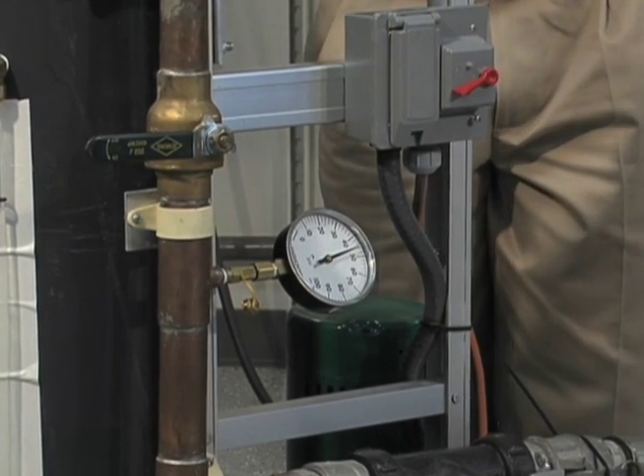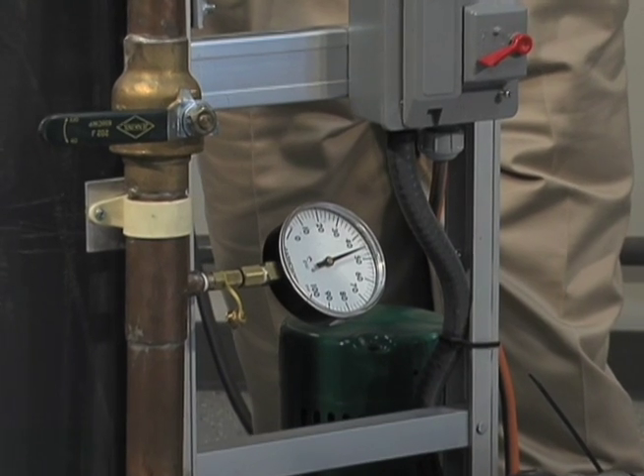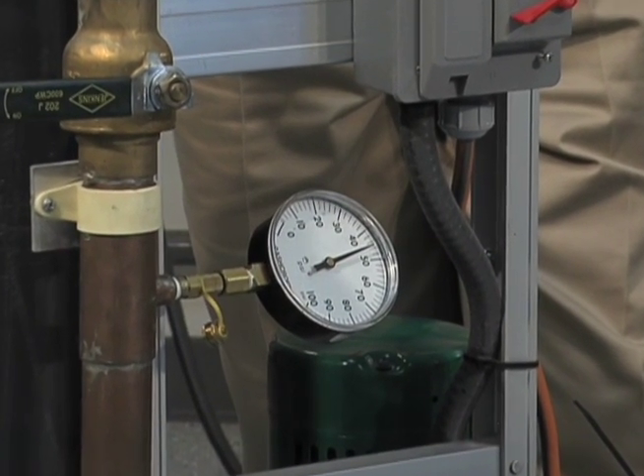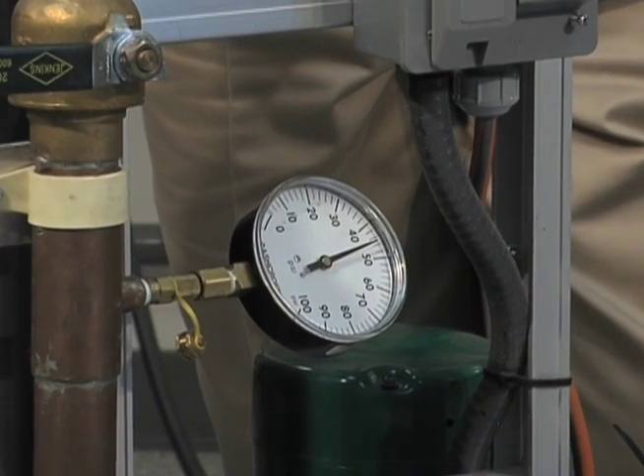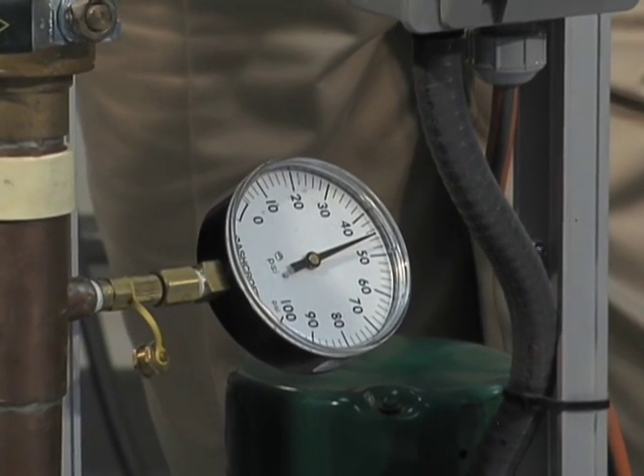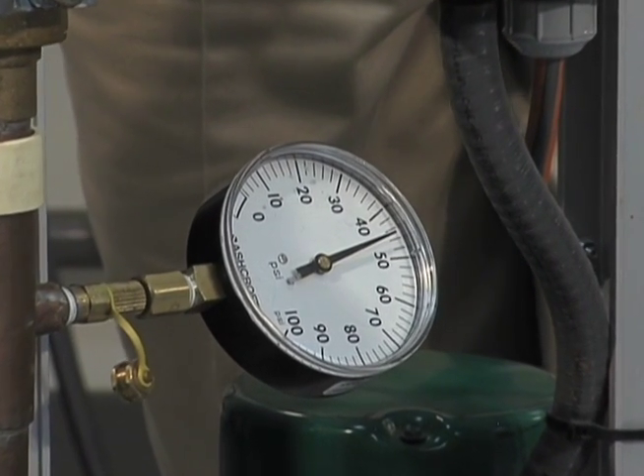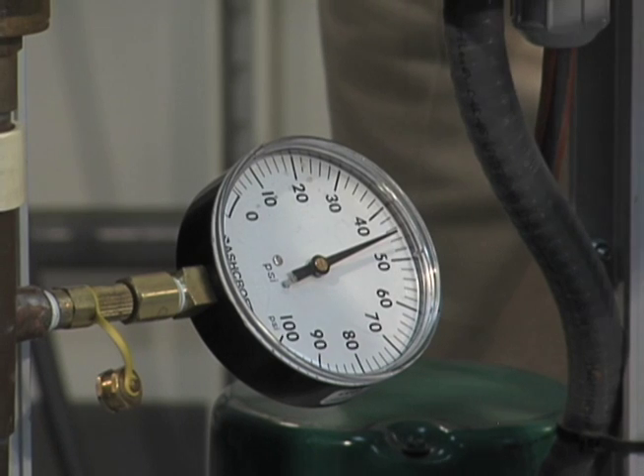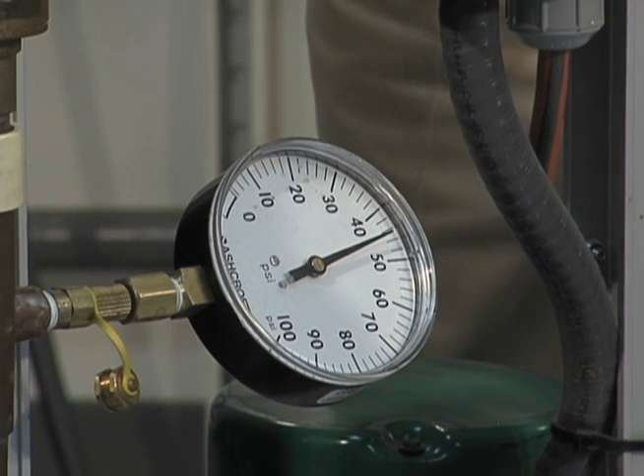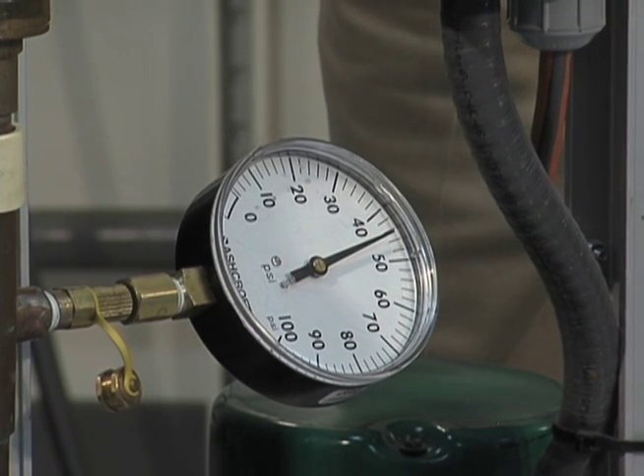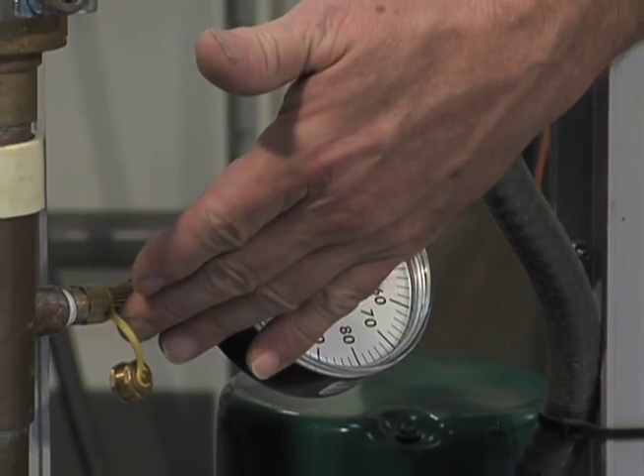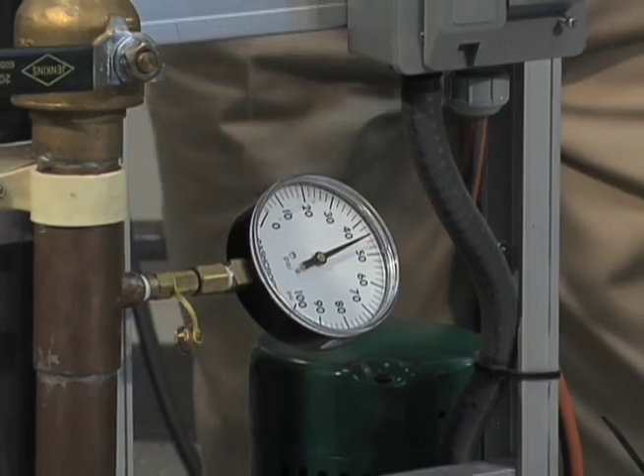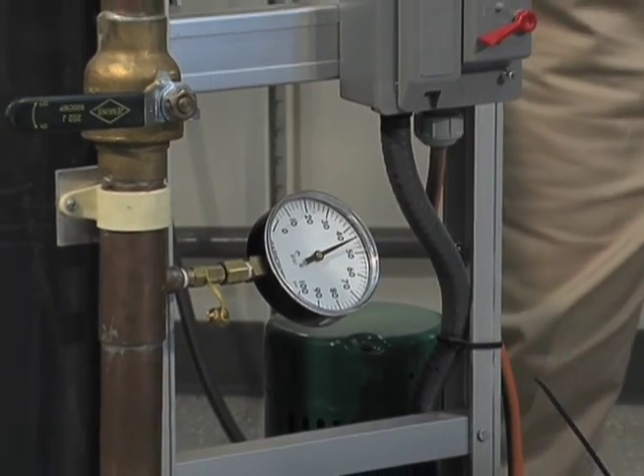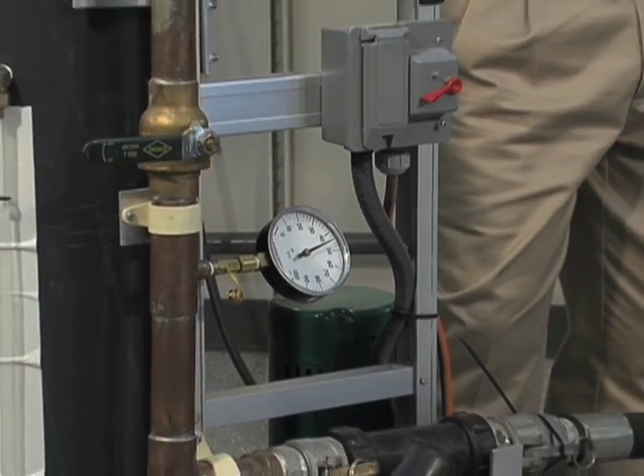If we have an excessive amount of air in there, we're going to see some movement on that needle. It's not unusual to see a little bit of creep on that needle over a few minutes just as things start to settle down. If you have any components on your flush cart that may leak, you may want to reconsider and take this pressure gauge out. Again, it slides through that PT port, and install it over here at the PT port of your heat pump.